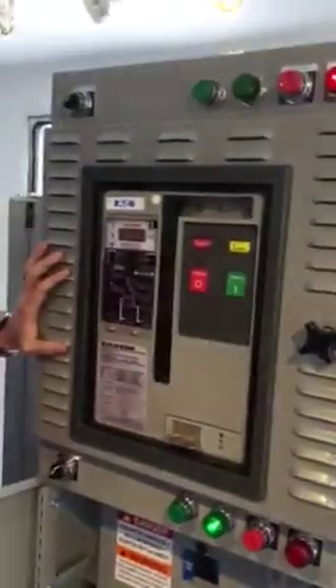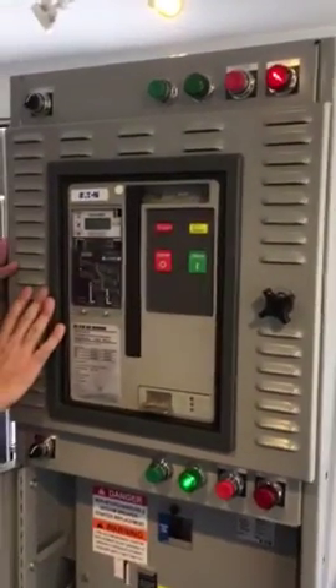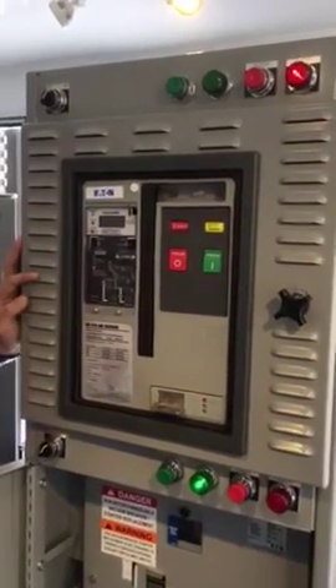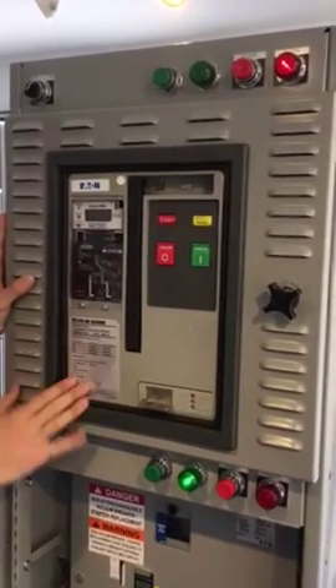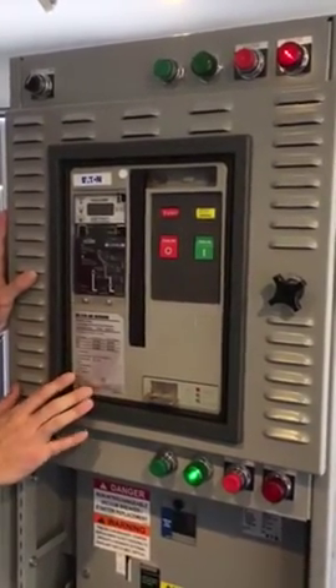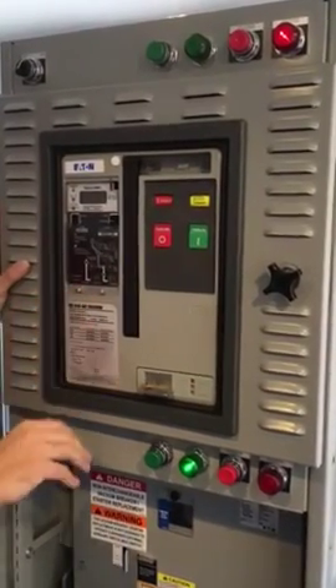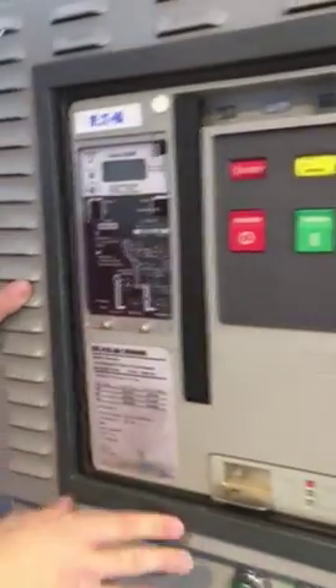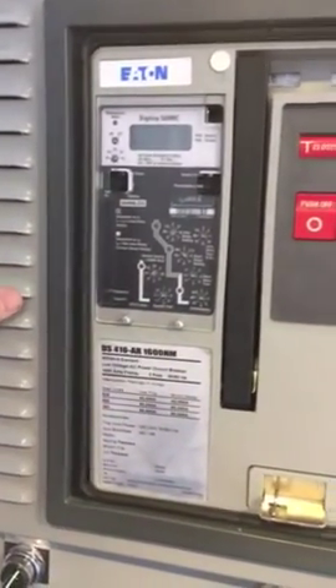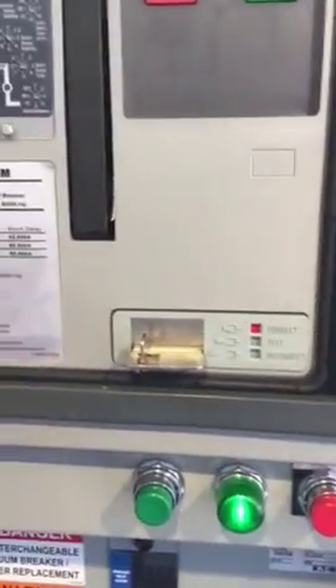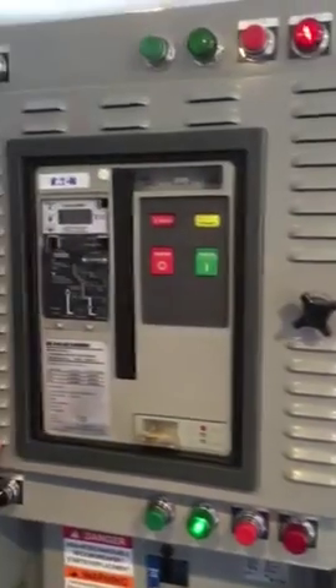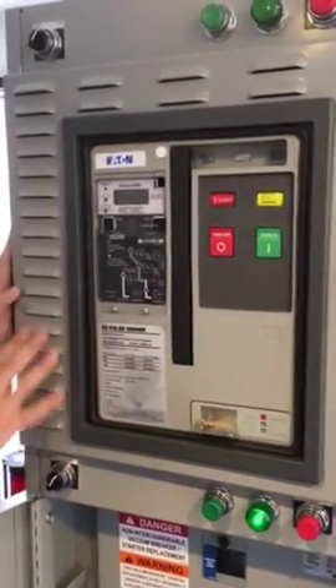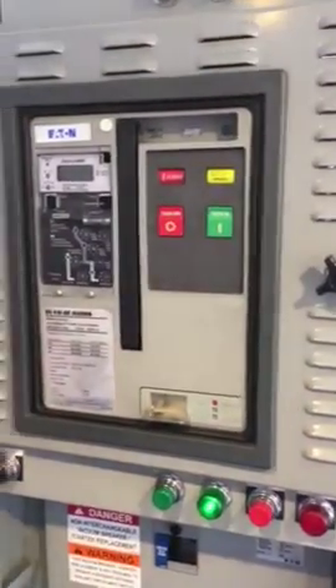Then at the top here, we have the retrofit from the DS to the bolt-in Magnum, brand new Magnum breaker. Value add options here are parts are really easy to get for the Magnum breaker right now. We have a lot of communication options in the trip unit, and also from a customer perspective, you can rack this breaker in and out of the cell with the door closed. Okay, as you noticed before, if you want to rack out that DS breaker, you have to have this door wide open. Everything here is held behind the cover, and this is obviously a NEMA 1 cover with a lot of venting on it. You can get this in different configurations as well.